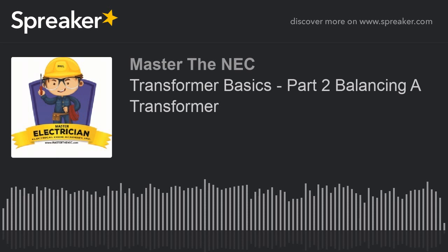Now, let's go on to when we're dealing with those 120s. On those, I put 120 volts 100% on C1 or C2. But remember, that's utilizing the C phase only because that is the one that we're going to put these loads on. And we're trying to balance it out, because at this point we don't really have anything placed on there except for the 7,000 VA that we did for balancing out that 42 kVA load.